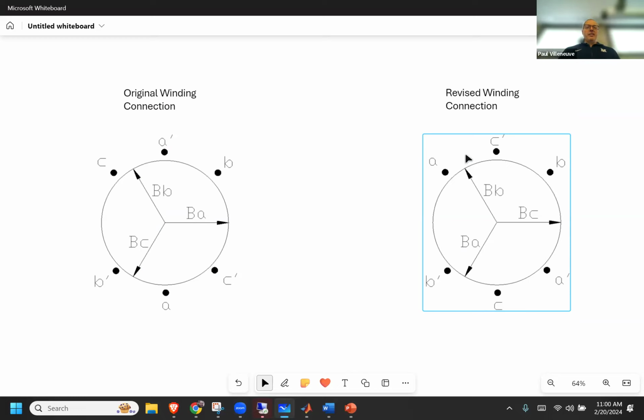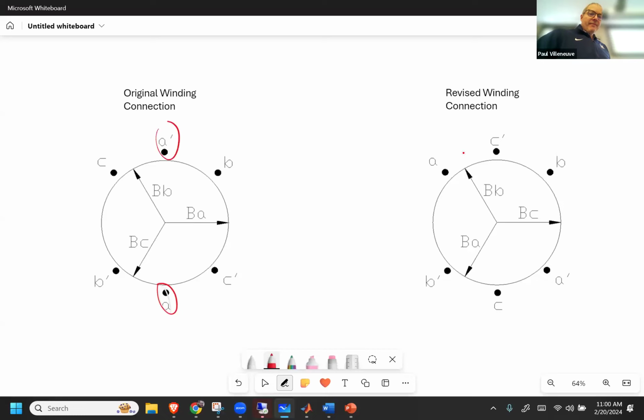All we're doing is taking A and C and swapping them. Literally, when you walk up to a motor, you've got 3 incoming leads from your power source, and the motor has 3 wires coming out, connected in delta or Y, whatever they need to be. You can connect it any way you want. We originally connected the motor as shown on the left, and now we're going to take A and C and swap them around.